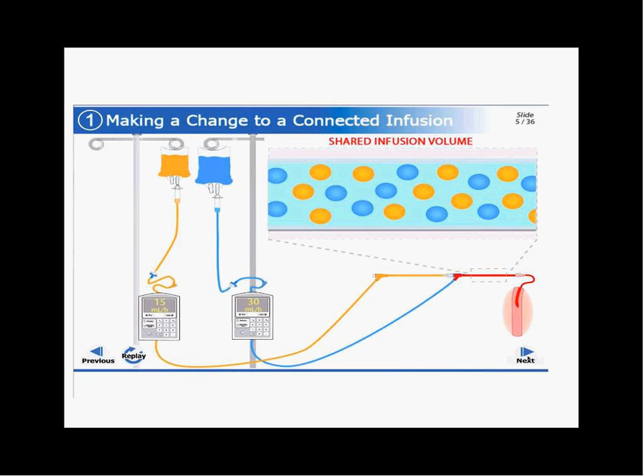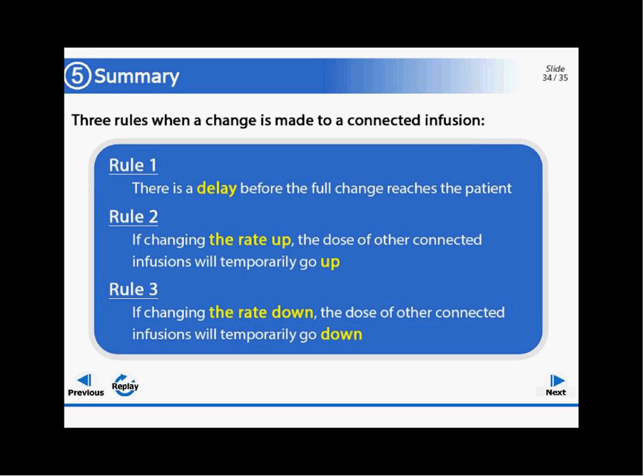Based on the theory, we then bring it back up a level and summarize by creating these 3 rules to help clinicians develop their conceptual model so they can quickly predict what will happen when they're making a change to a connected infusion and the impact it may have on a critically ill or pediatric patient who may be more sensitive to infusion consistency and accuracy. So the 3 rules are: when a change is made to a connected infusion, there's a delay before that full change reaches the patient. 2, if you're changing an infusion rate up, the dose of the other connected infusions will temporarily go up. 3, if you're changing the rate of the connected infusion down, the dose of the other connected infusions will temporarily go down as well.